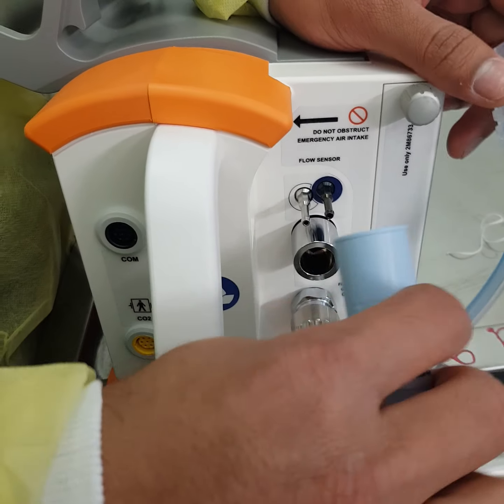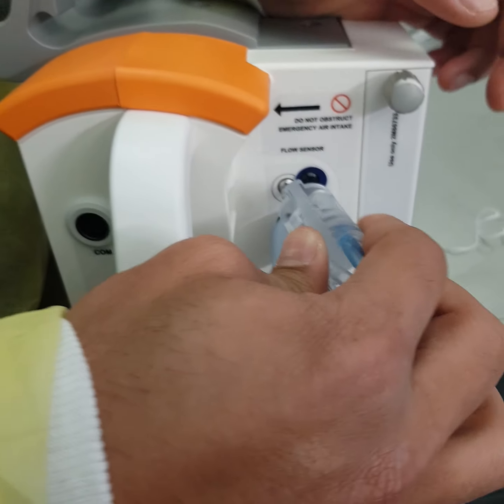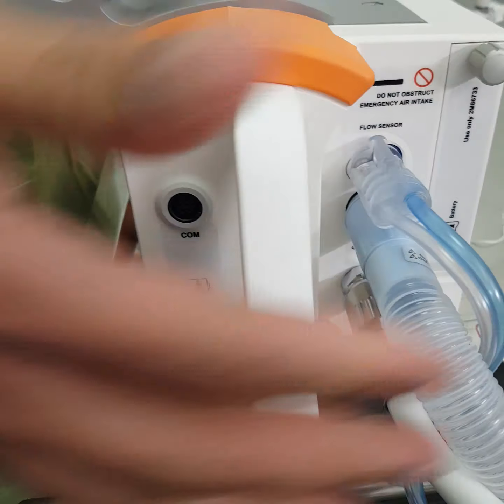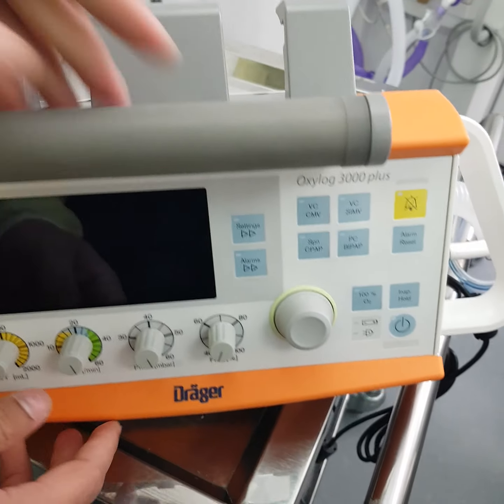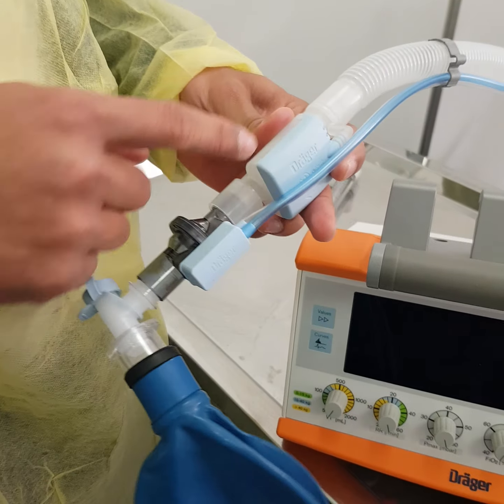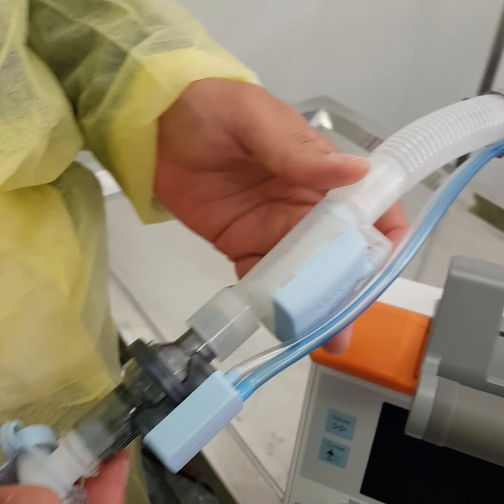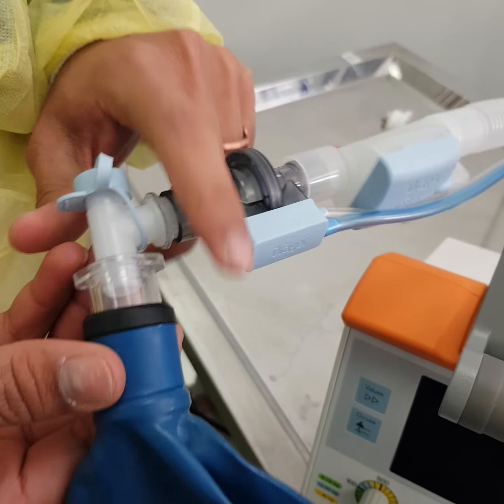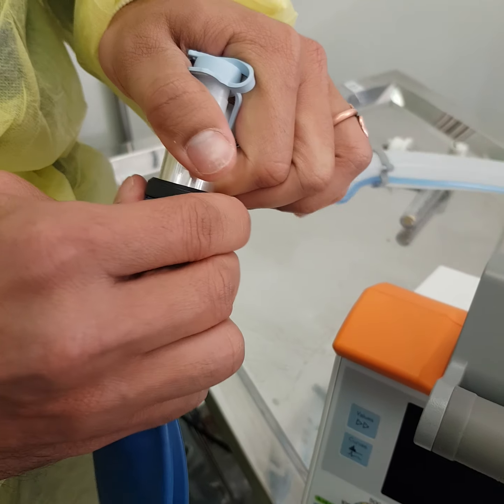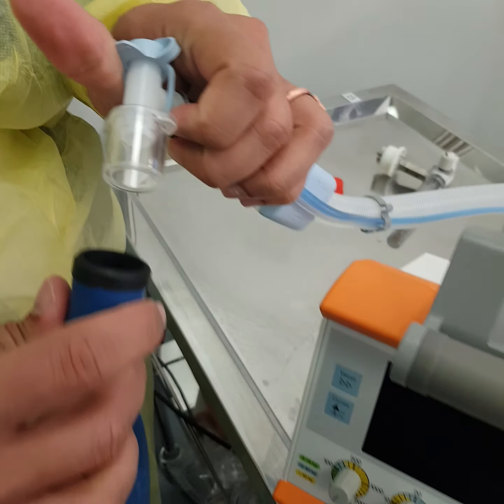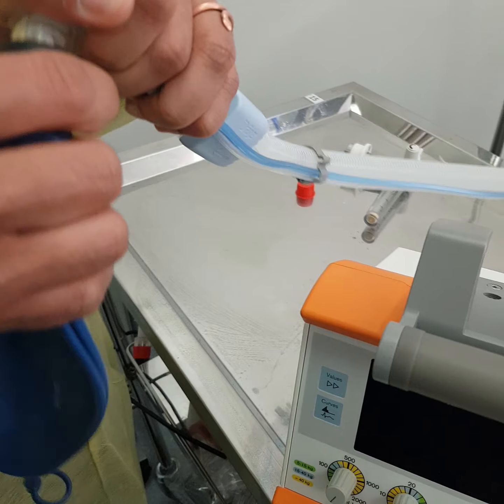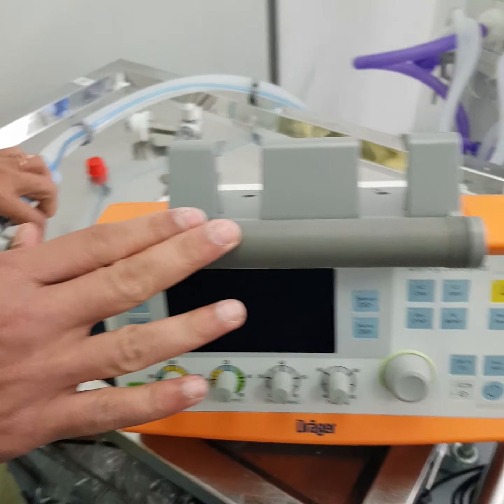Reusable, exactly. Thank you, Engineer Jagan. So this can be fixed over here. Once it is fixed, you are ready for the connections and assembling. Everything is ready. At the end of the circuit, we are going to connect the patient, because the disposable circuit is inbuilt with the expiratory port and the flow sensor. So the only thing you have to do is connect to the patient's ET tube or the NIV mask, because this device can be used for non-invasive and invasive purposes.